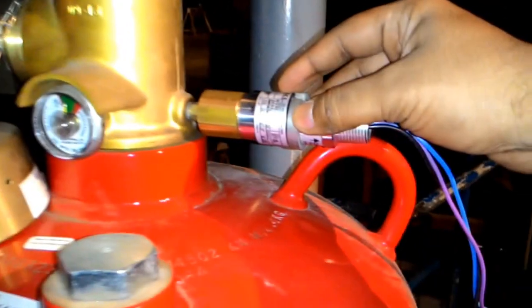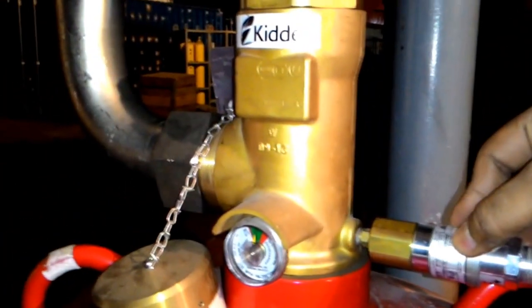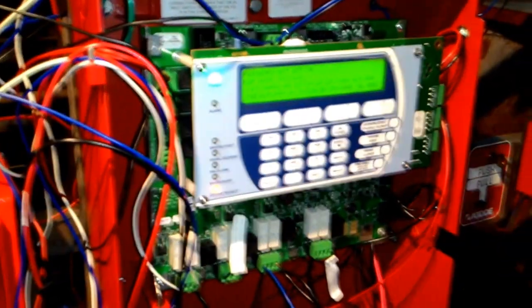As you can see, we have the supervisory pressure switch connected to the cylinder's head which goes in loop to an addressable module connected here, which is in turn connected to the SLC loop connected to the TD panel.